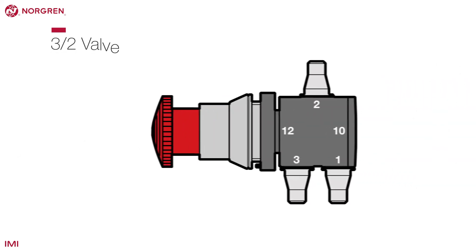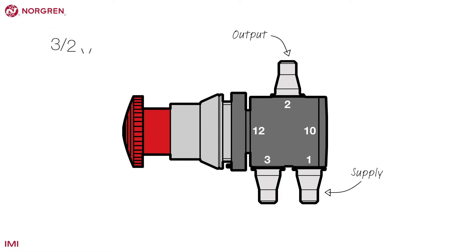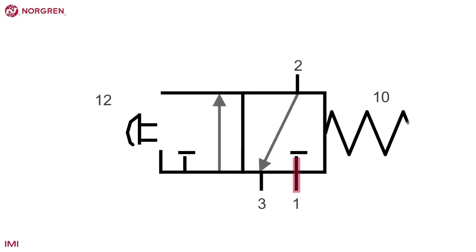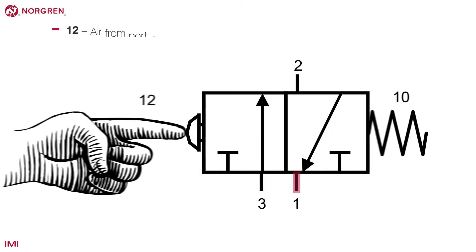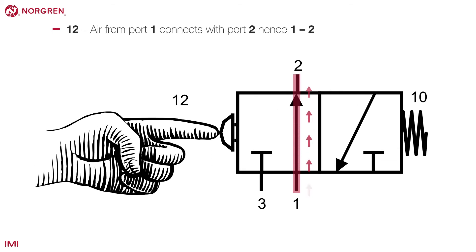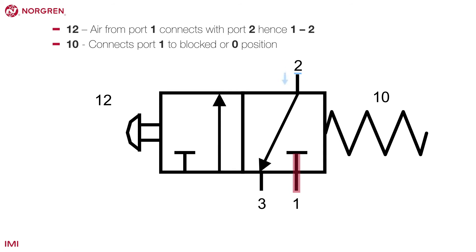A 3-2 valve has 3 ports and 2 positions. It works in a similar way to the 2-2 valve, but with the addition of an exhaust labelled as port 3. This valve also has 1-2 and 1-0 positions. However, when in the 1-0 position, the air from port 2 is vented through port 3.